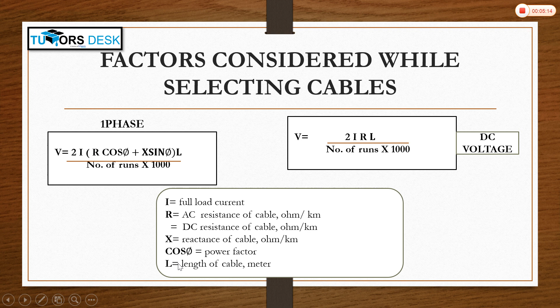Here, I is the full load current, R is the AC resistance of the cable in ohms per kilometer for AC supply, and the DC resistance of the cable in ohms per kilometer for DC voltage. X is the reactance of the cable in ohms per kilometer. All this data is given in the manufacturer's catalog. Cos phi is the power factor of the load, and L is the length of the cable in meters.